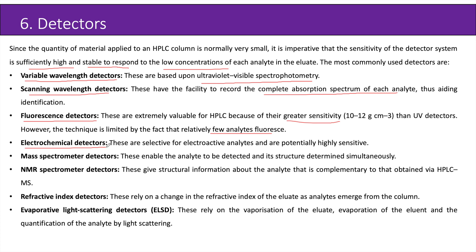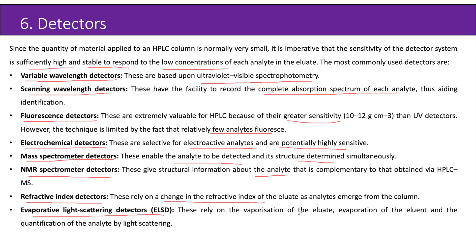Electrochemical detectors are selective for electroactive analytes and are potentially highly sensitive. Mass spectrometer detectors enable the analyte to be detected and its structure determined simultaneously. NMR spectrometer detectors give structural information about the analyte that is complementary to that obtained via HPLC-MS. Refractive index detectors rely on a change in the refractive index of the eluate as analytes emerge from the column. Evaporative light scattering detectors (ELSD) rely on the vaporization of the eluate, evaporation of the eluent, and quantification of the analyte by light scattering.